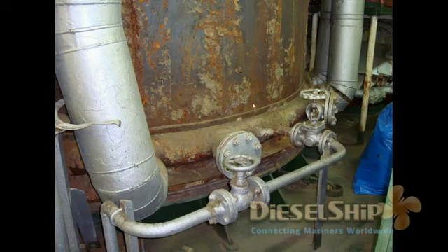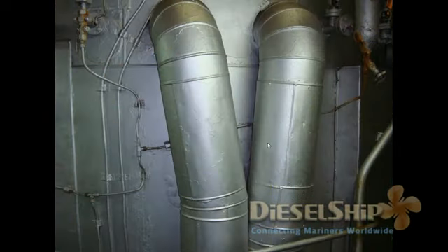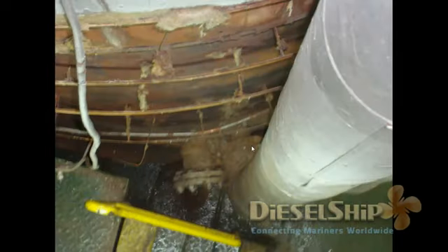And from the water ring you have tubes inside the boiler which generate steam and then put it back to the steam drum. And what you see over here is the hand hole, and after emptying the boiler you can open this and clear the sludge out. And these are the blowdown valves. So we have two valves over here. These are the bottom blowdown valves. Let's see some more pictures. Yeah, so this is another view of a downcomer, completely insulated. So one more picture, two downcomers which are huge, just to maintain the ratio of 4:1. And just a top view from the top. See how big the downcomer is, connecting the water ring at the bottom.